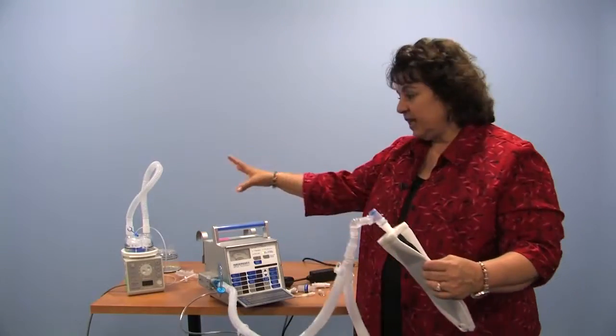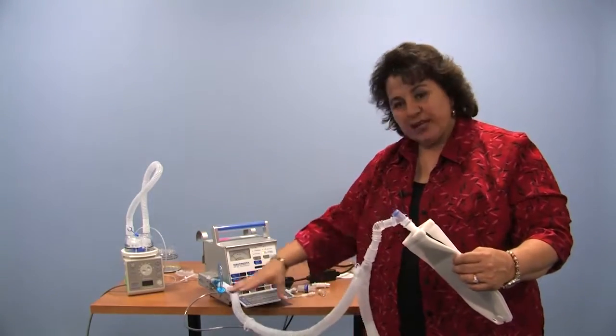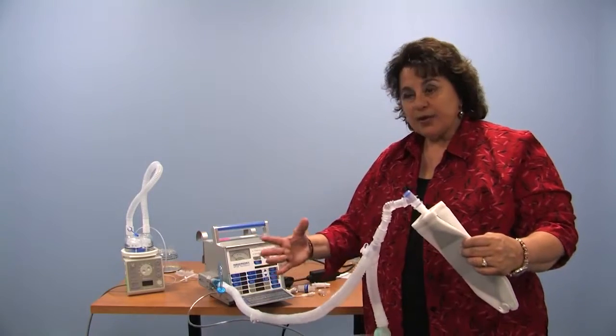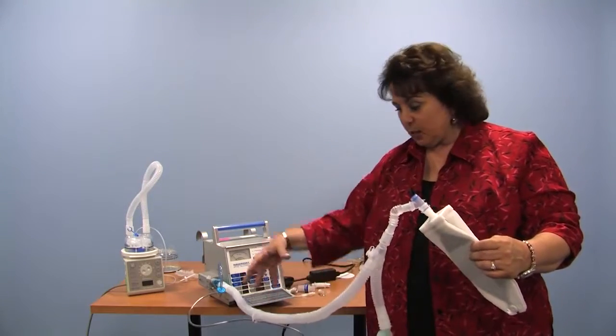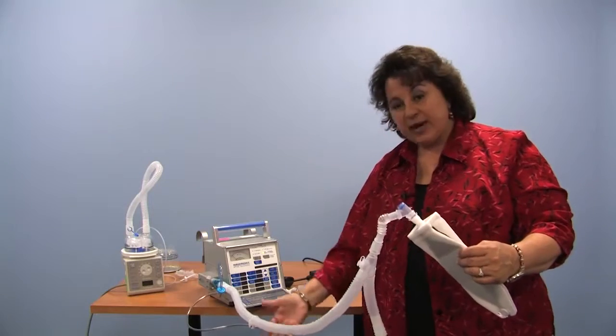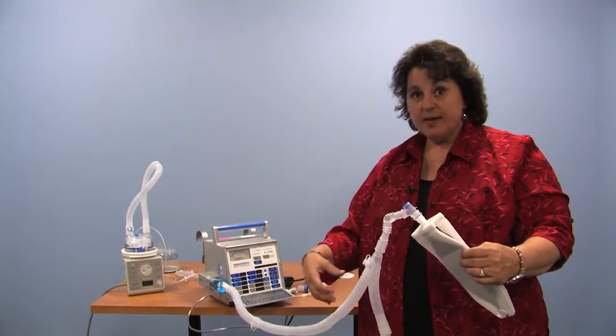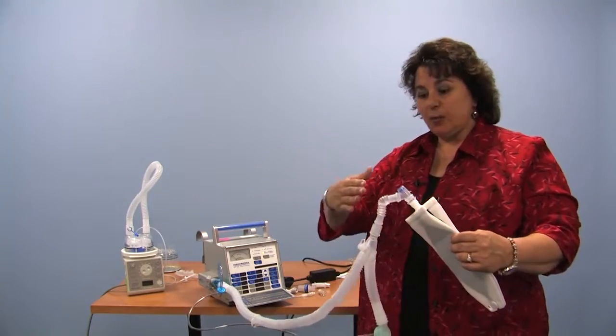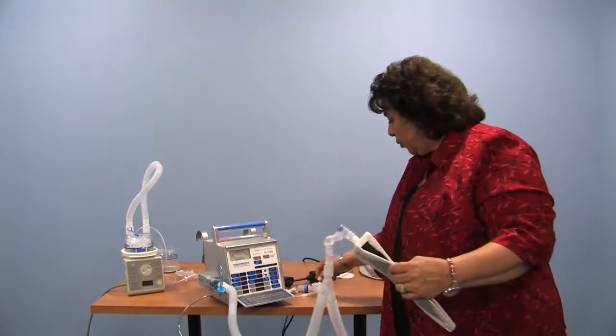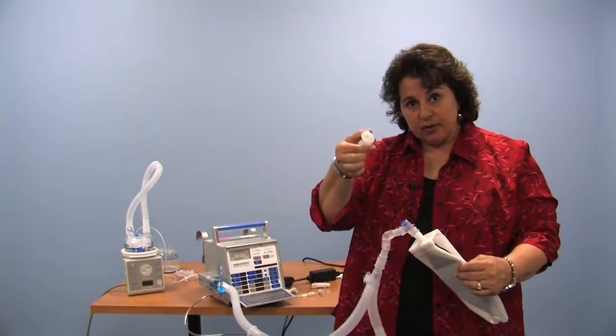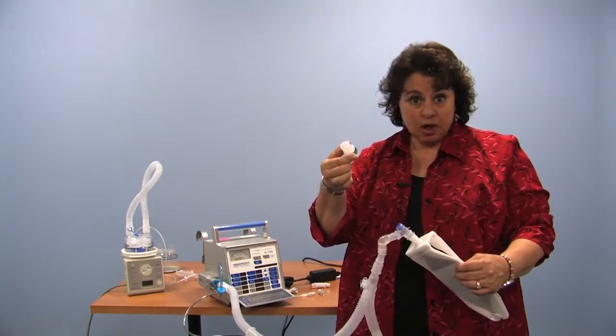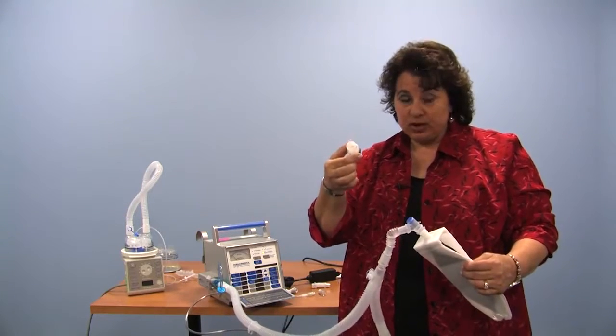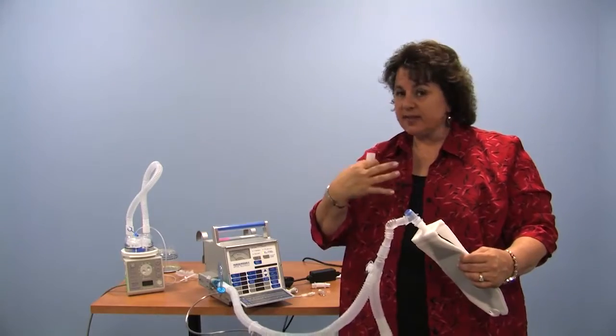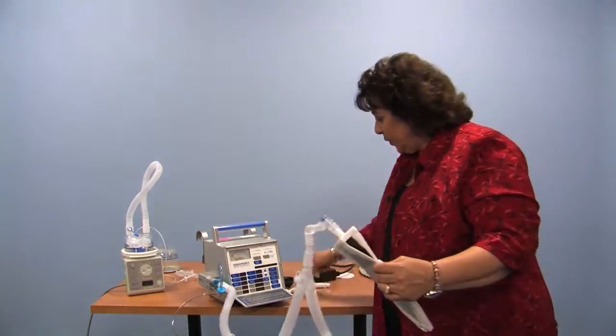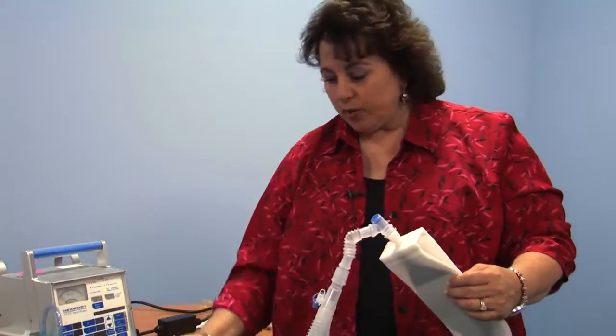If you're going to use the heater, if we don't use heated wire hoses, there is a hose with a water trap in it that we can have the water be dependent and drain into a water trap that we have to empty. That's another option. So we can have what we call the dry circuit for travel. We can add the heat moisture exchanger. That could be 24/7 for a larger adult adolescent patient who has a larger trach tube and doesn't have a problem with thick secretions. We could move next to a humidifier with a water trap in the hose, which means you have to drain it.